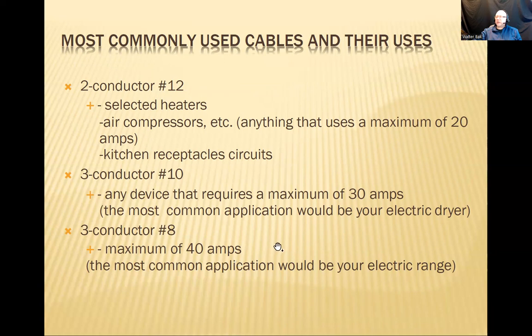So here's how it goes. If you have a cable running in the wall, and let's say it was 14-2, and you need to connect an air conditioner to it, then you could be out of luck a little bit, because you need 20 amps for the air conditioner. So what do you do? You go and replace the circuit breaker with a bigger one. Instead of a 15 amp circuit breaker at the electrical panel, you would put a 20 amp circuit breaker, and you would install a receptacle that physically fits the 20 amp plug that comes with the air conditioner unit, where one of the prongs is sideways. Well, and then you're good, right? Well, wrong, because you still have that wire in the wall that is not thick enough. So don't ever do that. That's how fires start.